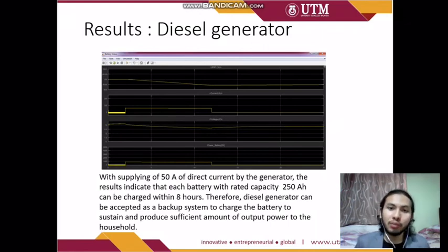As mentioned before in the methodology, there is load consumption between time 2 and time 12. That's why the state of charge of the battery is decreasing within that period. We also see an increase in current between time 2 and 12, indicating load consumption, while the voltage decreases, and the diesel generator turns on at time 12 to charge the battery.